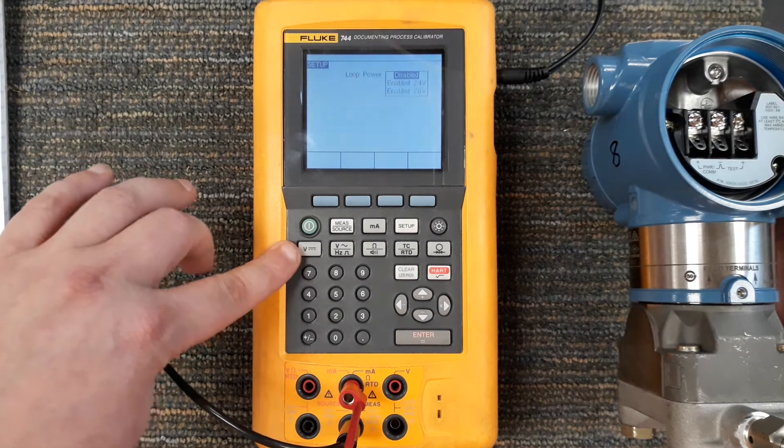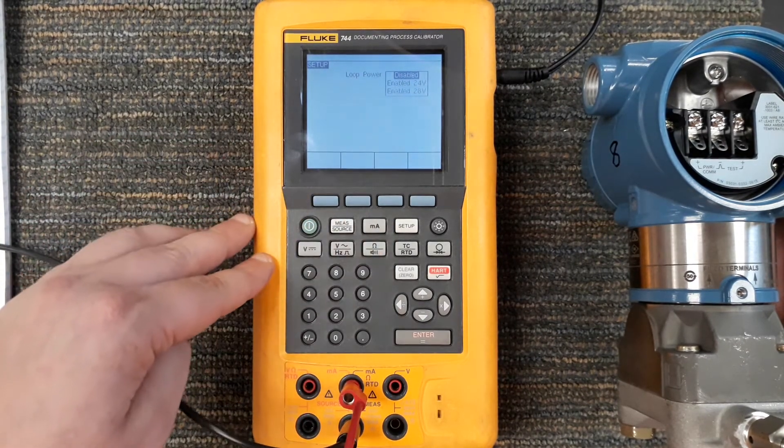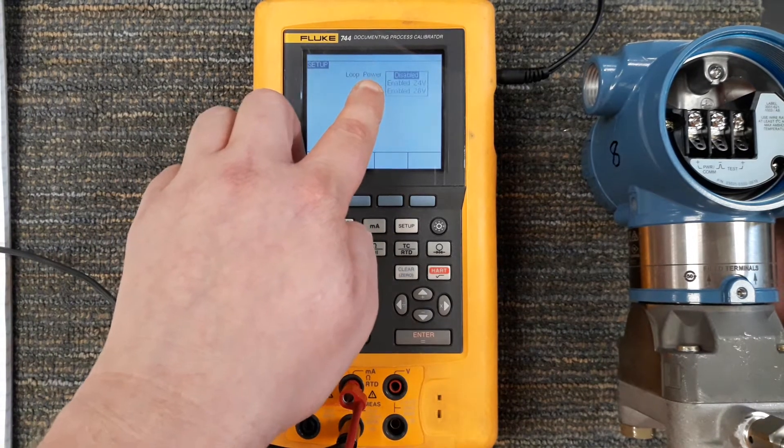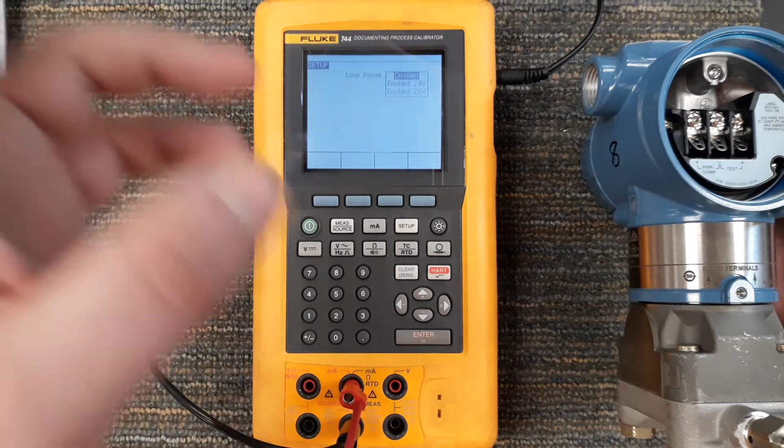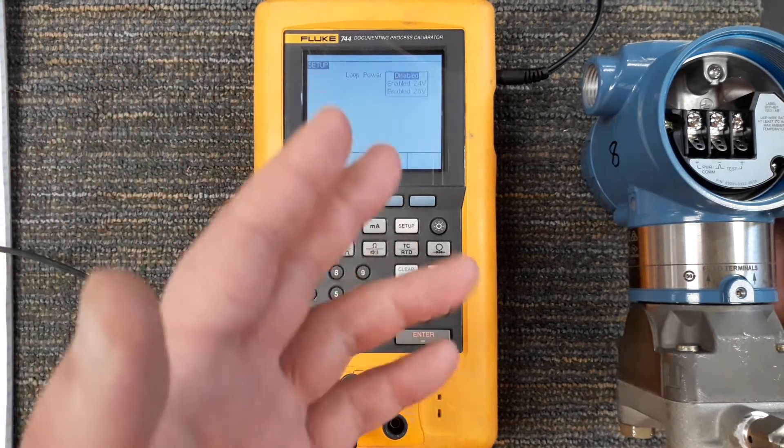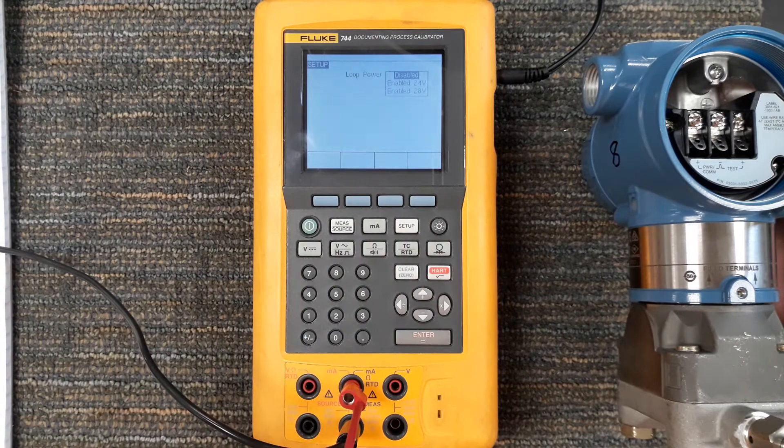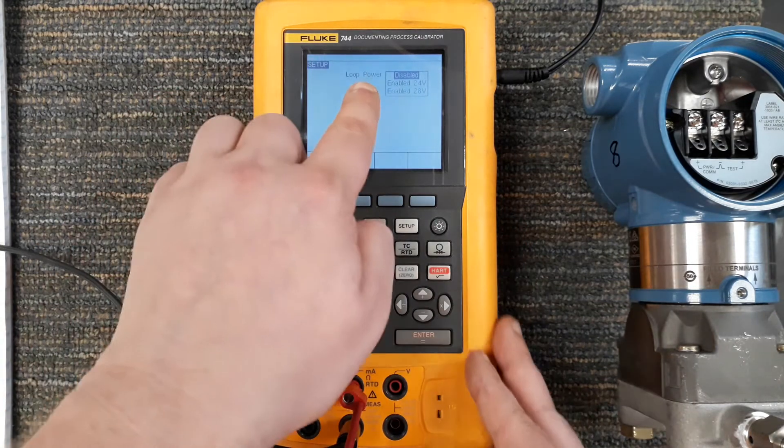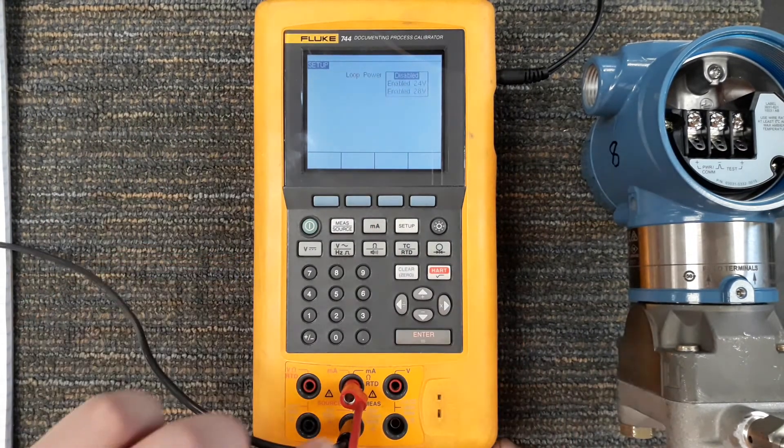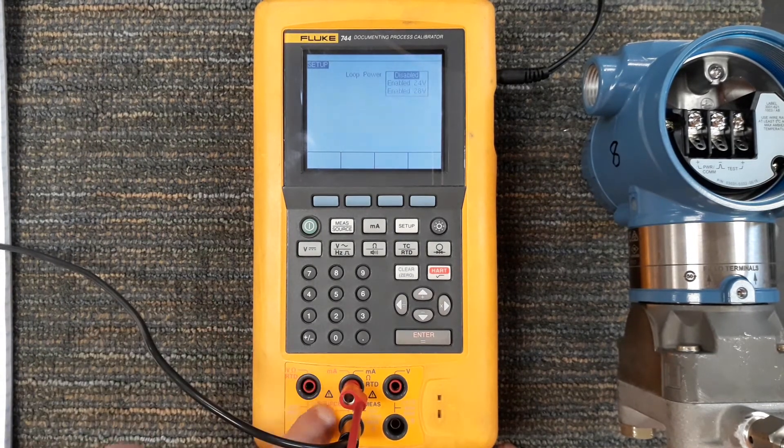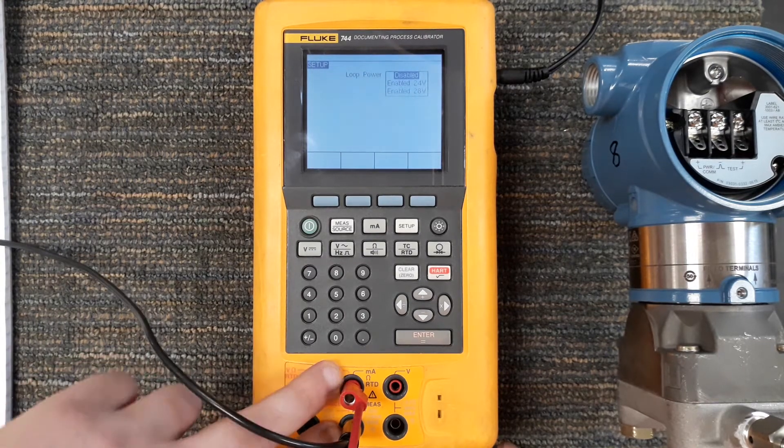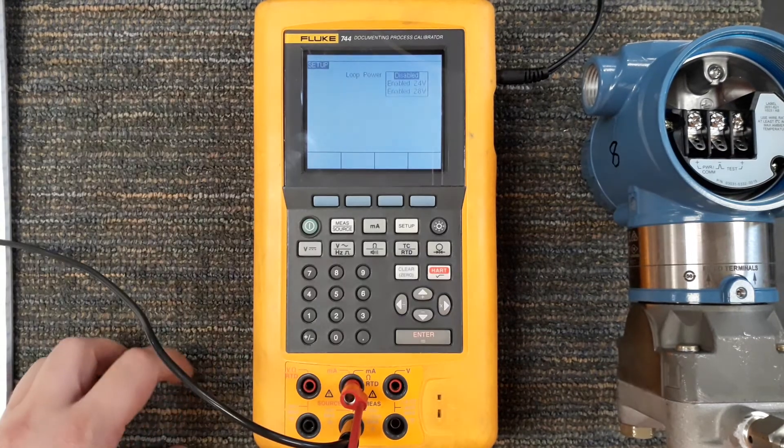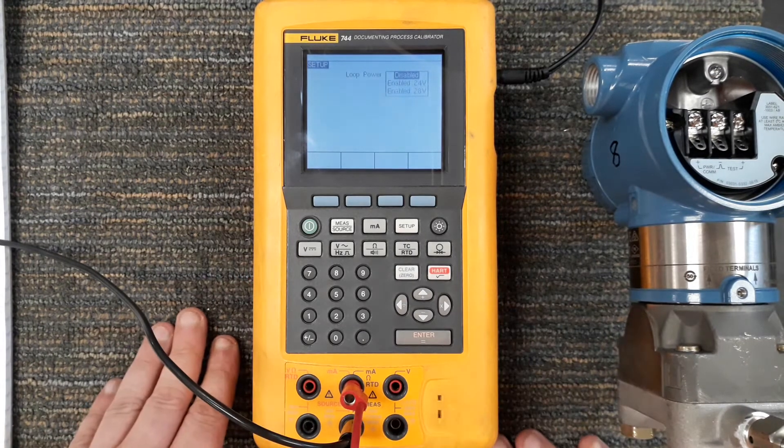I can have voltage without current but I cannot have current without voltage. So when I'm providing loop power I'm really concerned about providing current because in order to provide the current I have to be providing voltage. So this meter is going to provide loop power and if I pick the 28 volts I'm actually going to plug into where it says source milliamps because I'm going to be sourcing current in order to source loop power. That is one of the things that's confusing.